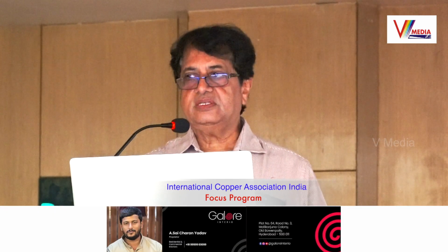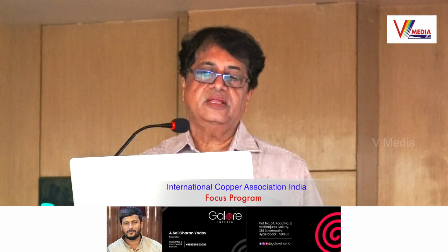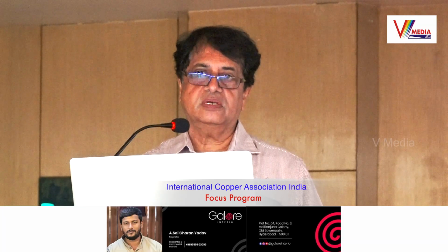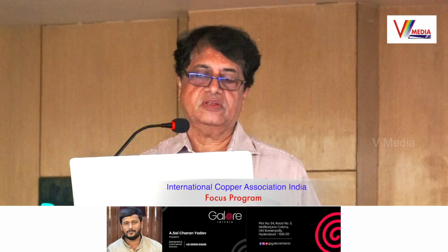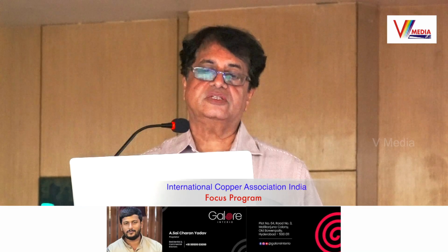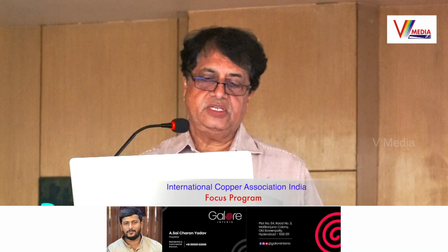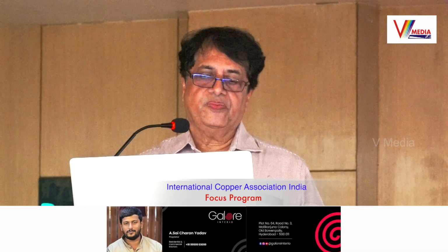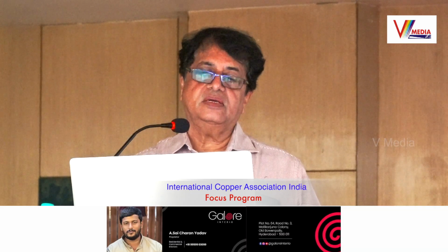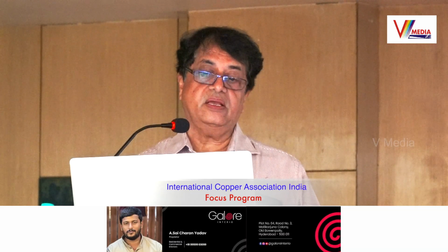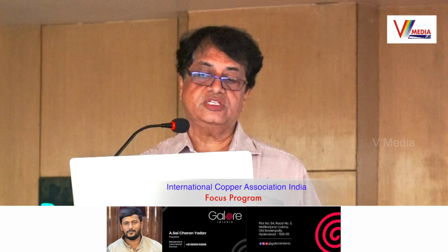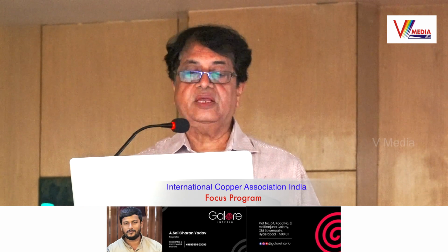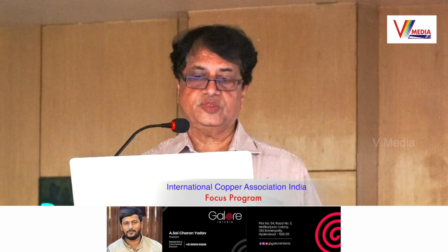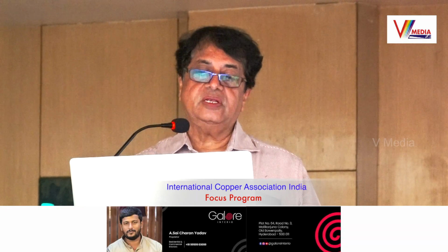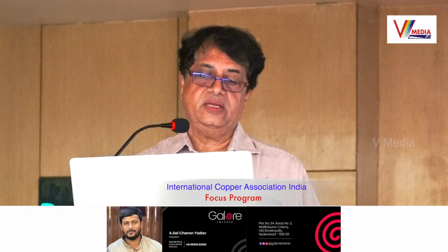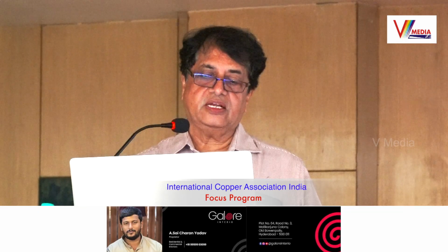So in these regulations, under regulation number 38, they have mentioned that in the service shaft, instead of electrical power cables, the bus duct shall be used. So if you see here, this is the bus duct. Because electrical cables may spread the fires, because the insulation may catch fire. The insulation of the cables may be toxic. It may generate some smoke also. So to eliminate that possibility, it has been made mandatory to use the bus duct in the electrical shaft.